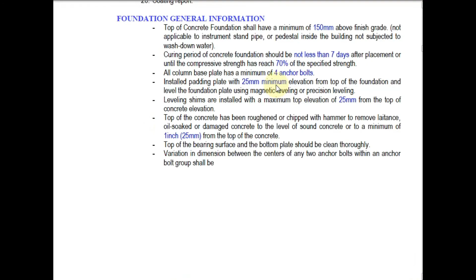Foundation general information. Top of concrete foundation shall have a minimum of 150 mm above finish grade. Not applicable to instrument standpipe, or pedestal inside the building, not subjected to wash-down water. Curing period of concrete foundation should be not less than 7 days after placement or until the compressive strength has reached 70% of the specified strength.